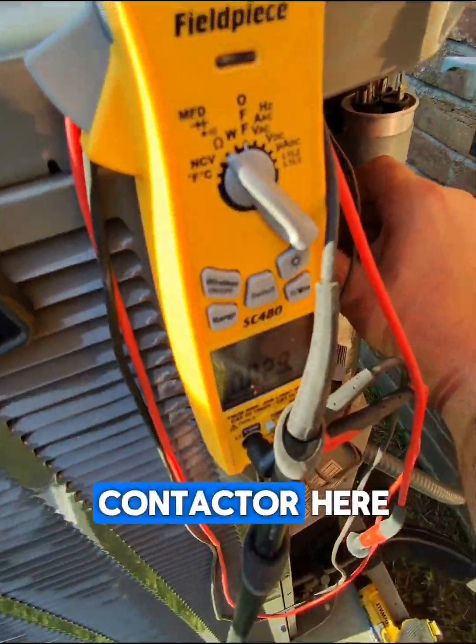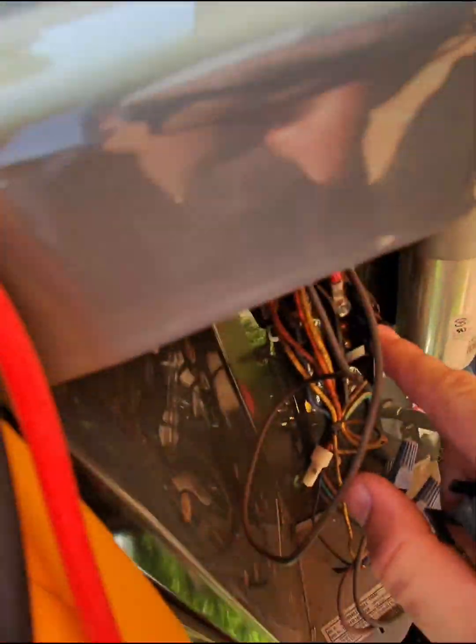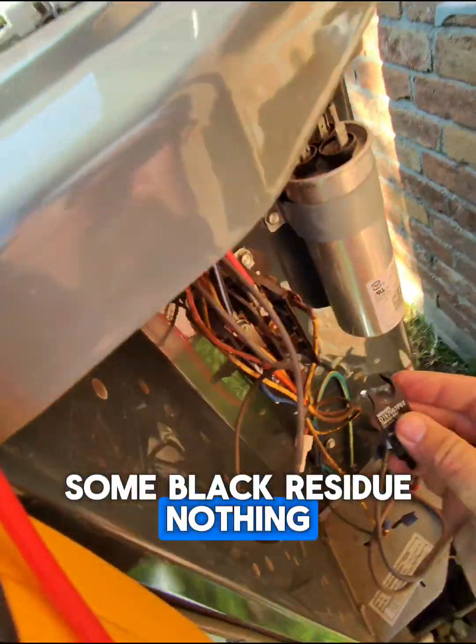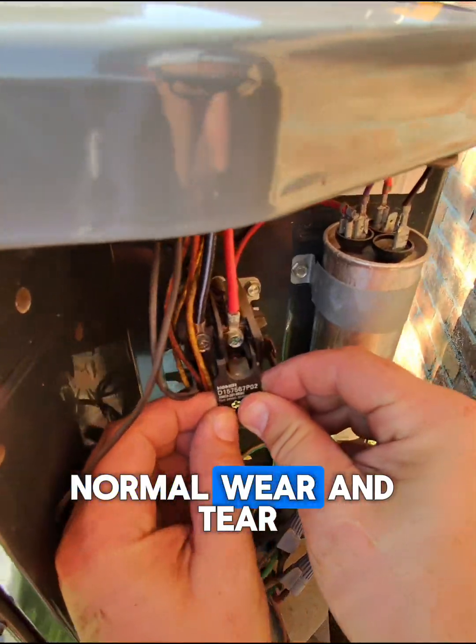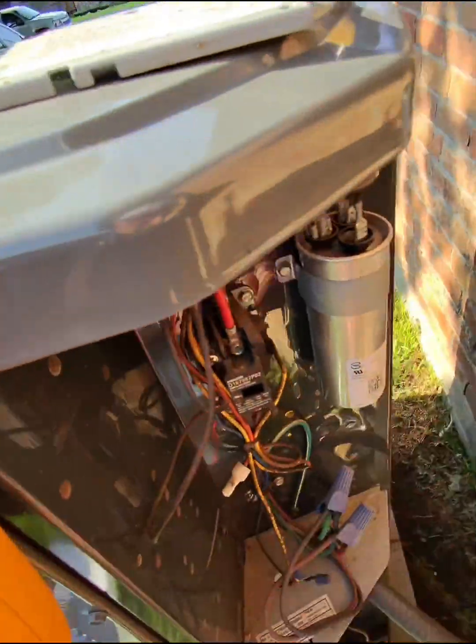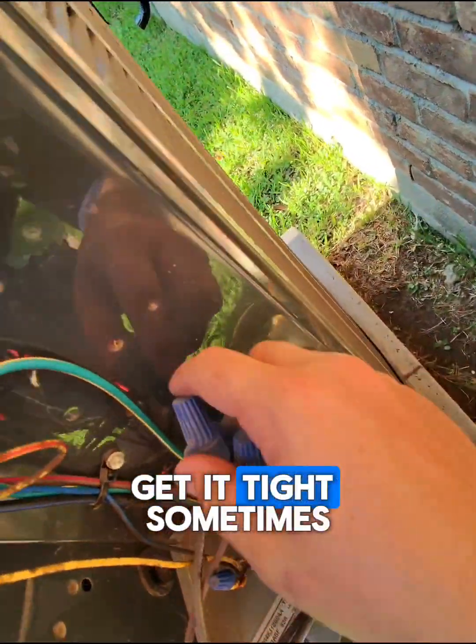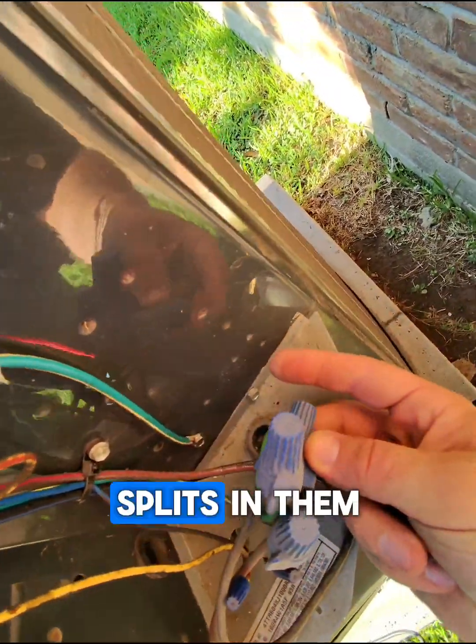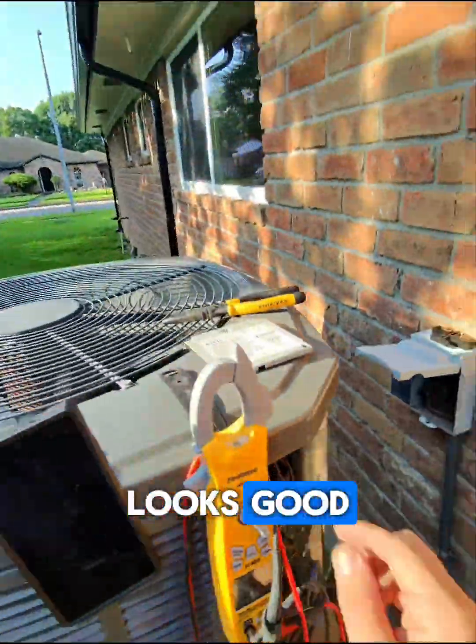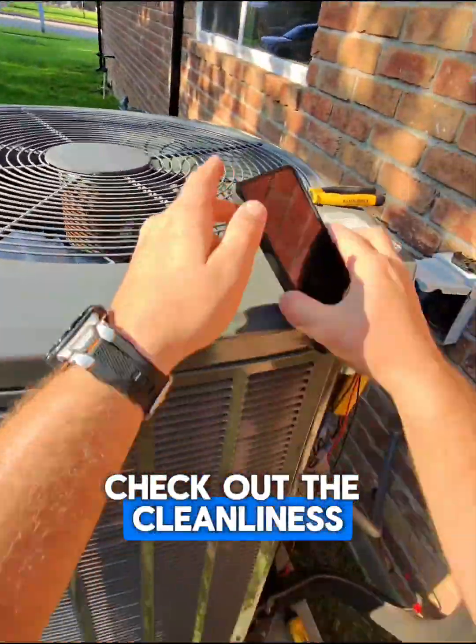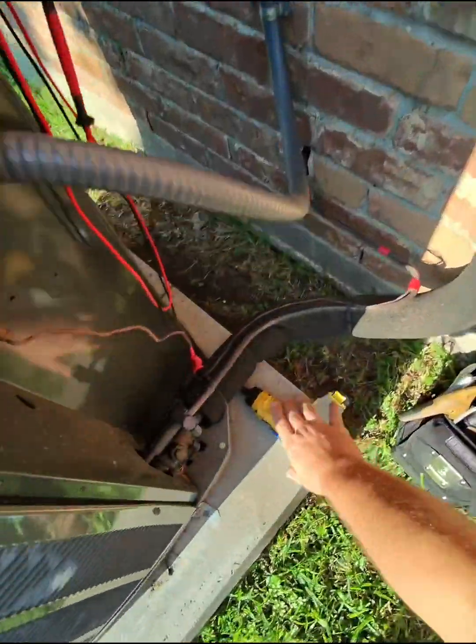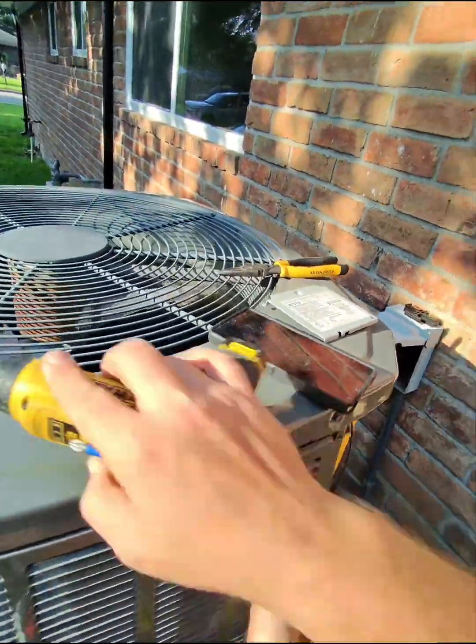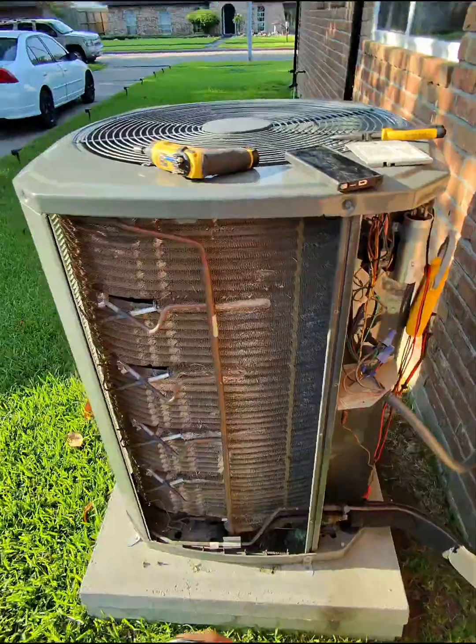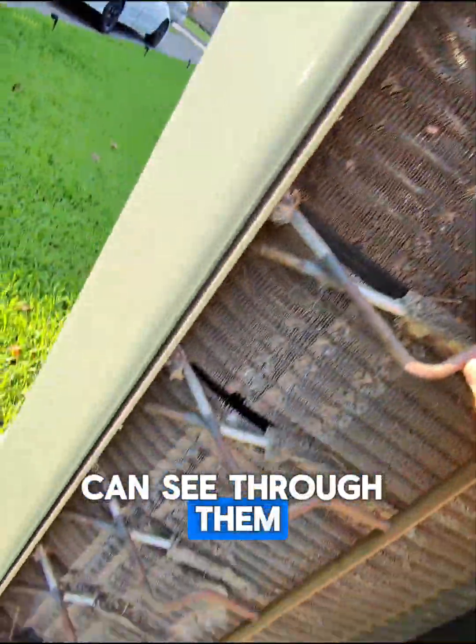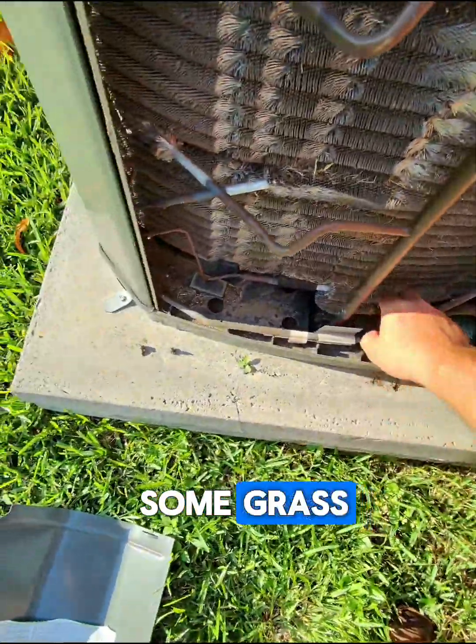Alright, got a contactor here. A little bit of pitting, some black residue, nothing too crazy. Normal wear and tear. Alright, good and tight. Sometimes you'll find these things overheated, splits in them. Looks good. Check out the cleanliness of our coils. You can see through them, not too bad. Light layer of dust, some grass, nothing too crazy.